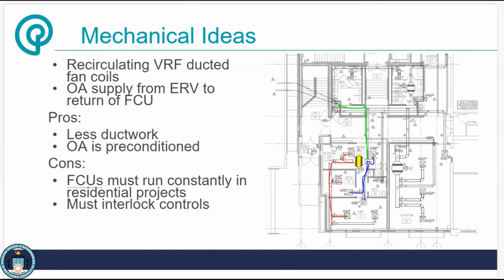This is much more common in non-residential projects, because in a residential project, to meet the requirement for continuous airflow in the space, you always need the fan coil's fan pushing air through to get the outdoor air where it needs to go. So it's a bit of extra fan energy if you use this setup residentially, though we don't see too much of that. For non-residential, combining the two works really well, and then it's just a matter of interlocking the controls to make everything work out okay.